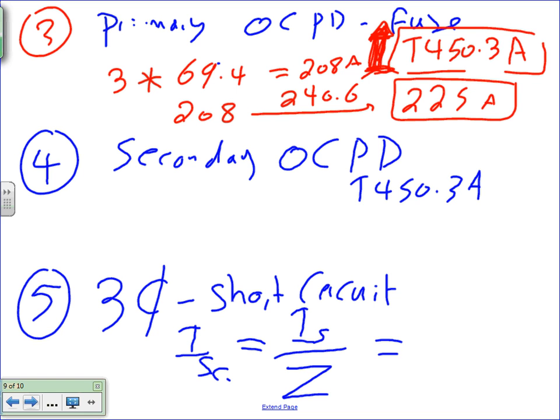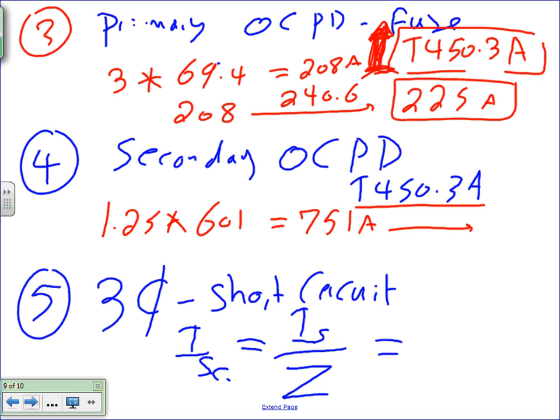Why did they go up? Because there's note number one. If you go to the table, guys, underneath it says, if you don't hit the jackpot and you hit an actual standard, you are allowed to go up. You don't have to. On the test, if you don't go up, I will dock you guys, because that is the maximum overcurrent protection device. The secondary is a piece of cake, guys. Based on the same table, you go 1.25 multiplied by 601, and like my friend says, 751 amps. Take this one to section 240.6, and that will get you an easy 800 amp circuit breaker or fuse.